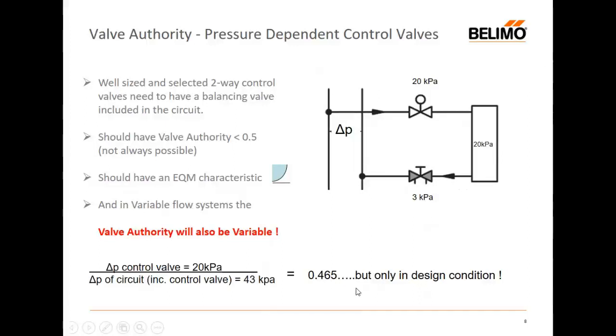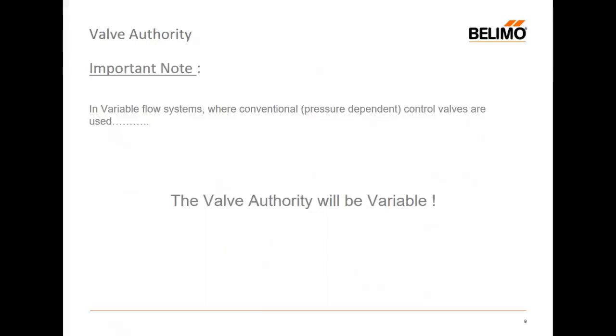0.465. But that is only in design condition, on the day of commissioning or when all the valves are fully open and at full demand, essentially. And if we change the flow rates, of course, all those pressure drops and those calculations will need to change. So it's very important to understand that where I'm using conventional control valves in a variable flow system, even if I'm using manual balancing valves, the valve authority is going to vary. It's going to vary because I'm in a dynamic system. And so the valve is going to have to respond when the balancing valve is not able to.